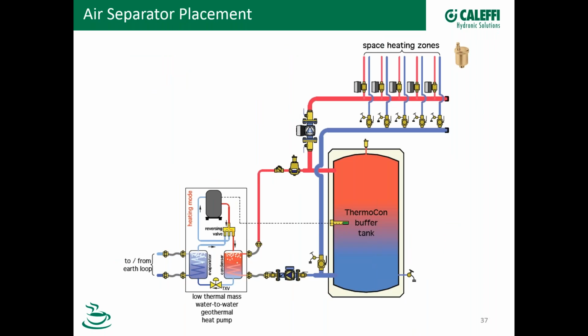Okay, another schematic, just a variation here. This is a geothermal heat pump. So right in the middle, we can see a good location for an air separator, right coming out of the buffer tank, also in the same supply line here. This one's perfect because it's on the suction side of the pump, so that's a great location for this one. And then of course, as we have heating zones, if we have any high points out in that piping, you want to put air vents out there too.